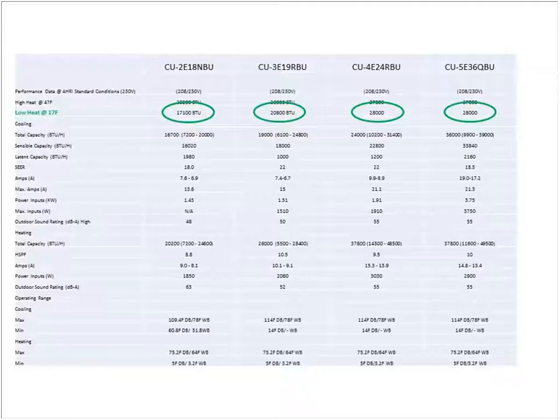Because the best system, it's hard to define what a best system is, right? For one person, this might be the best system, but another person could have a whole different house, and now all of a sudden the wall mounts don't work, or the cassette does work, and so forth. So there's no such thing as a global best system. There's what's right for you. What you're going to look at is your cooling load requirement. And once you know your cooling load requirement, find out what devices are giving you, and what style you want. There's a certain personal style to it, whether it's the cassette, the concealed, or the wall mount. So when you say best, I'm not sure we can say what's the best. AHRI will tell you what will meet the requirement that you ask for as far as BTU loads. They won't tell you what would be the best selection. Does that make sense?